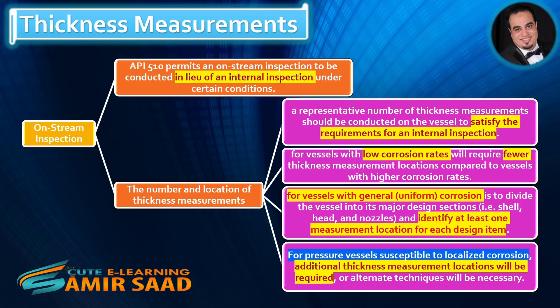Vessels with low corrosion rates will require fewer thickness measurement locations compared to vessels with higher corrosion rates. For vessels with general uniform corrosion, divide the vessel into its major design sections — shell, head, and nozzles — and identify at least one measurement location for each design item. For pressure vessels susceptible to localized corrosion, additional thickness measurement locations will be required, or alternate techniques will be necessary.